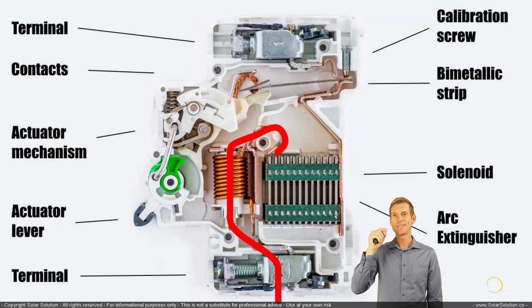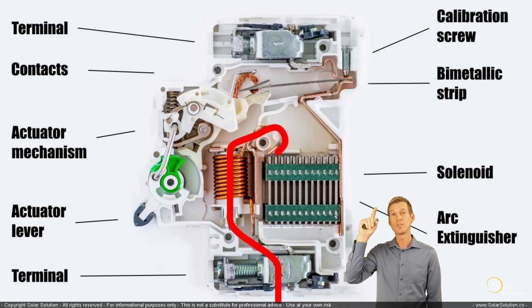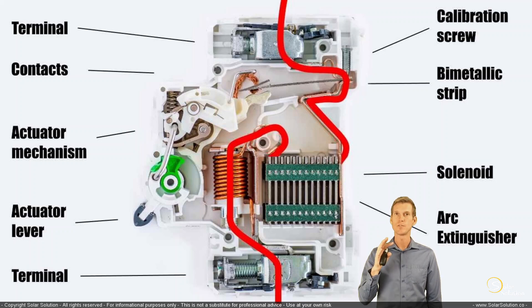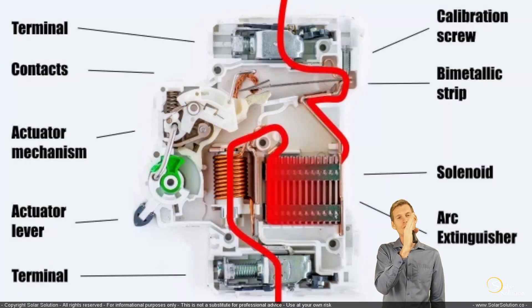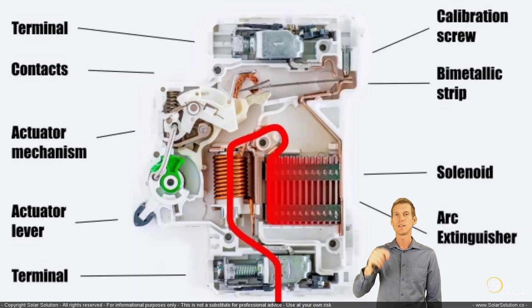Once the contacts open, the current has nowhere to go and must travel through the arc extinguisher to reach the top terminal. As the current tries to pass through the arc extinguisher, it makes very small arcs jumping from one plate to the next. These arcs lose energy as electrical energy is converted to heat and dissipated. Slowly the arc extinguishes, the current can no longer flow, and the circuit is safely interrupted.